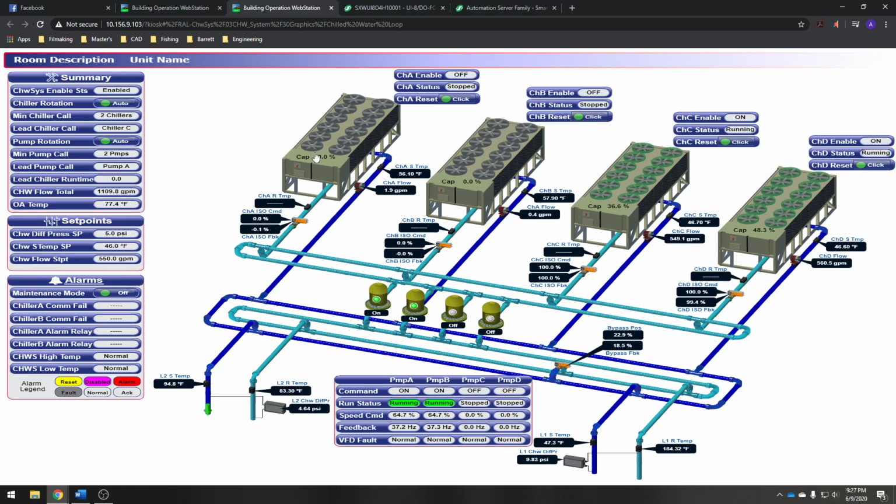It'll say, okay, chiller A has been on for 180 seconds, let's start the timer for 180 seconds to shut chiller C, since it's the lead, off. And by that time, this has already staged a couple compressors, and it's well on its way to maintaining the set point.